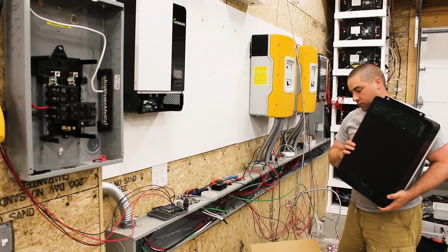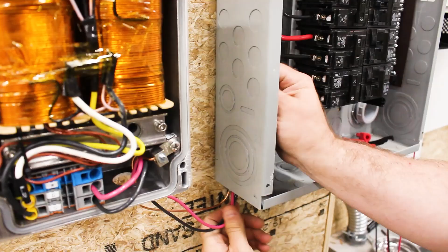This is actually the wiring for it. Now these 3 IMO disconnect switches, they can switch up to 1,000 volts, or I think there's even a setting on here for up to 1,500 volts, but you have to kind of derate it a little. But the point is that they're very high voltage disconnect switches. Now I'm running my PV in here more at about 300 volts. So these things can handle switching that off no problem.